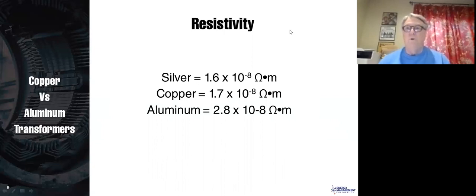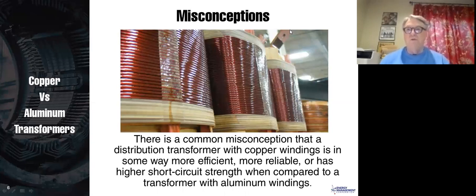And as you know, if you ever look at ampacity tables in the National Electrical Code, you'll see that aluminum wires of a certain size are going to have less ampacity than copper of that same size. But once you have an equivalent aluminum to copper with the same resistance, then they basically perform the same, they have the same losses, and it's not really a problem. So here's a transformer that has copper wires. You can see the kind of reddish color of copper there.